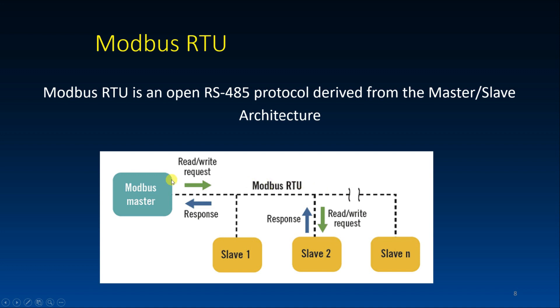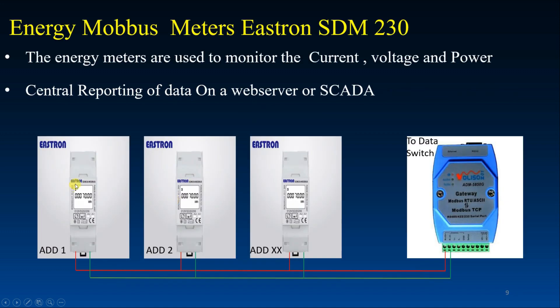Here is how data is sent between master and slave. The Modbus master sends a request — let's say to a temperature sensor at address 1. Only slave 1 responds; the other slaves won't reply because the message is addressed specifically to slave 1. To communicate with slave 2, the master sends address 2, and slave 2 responds. This is how multiple energy meters are set up, each with a unique address (1, 2, 3), all connected to the Modbus gateway via Ethernet.